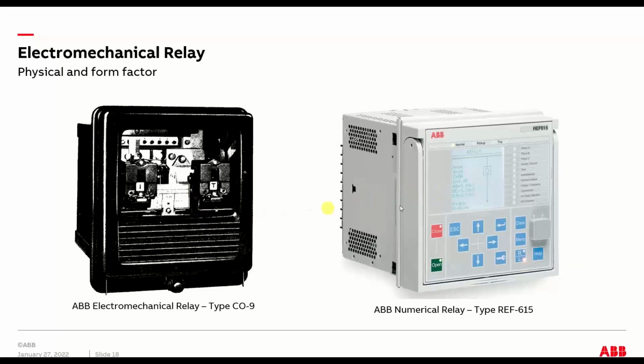Here's just kind of a comparison of form factor. These two relays are about the same dimensions. This might be a little bit bigger, but you can see there was a lot of intentional design on this to make it mimic this relay, because one of the interesting features is the internals of this relay are drawout. You can open this box, pull out this relay so it can be tested. Same thing here. This is a handle that pops out. So the back part stays within the gear, but you can draw this relay out, test it on a bench, or even just swap it out if you had a problem with it.